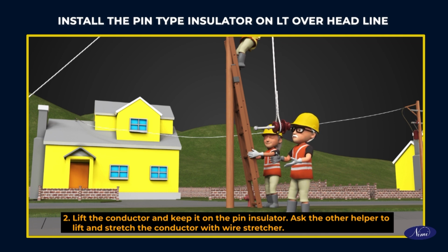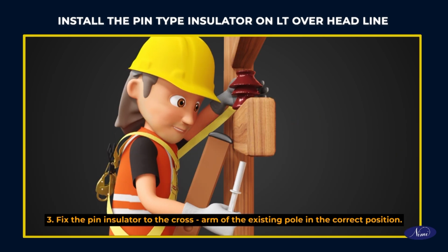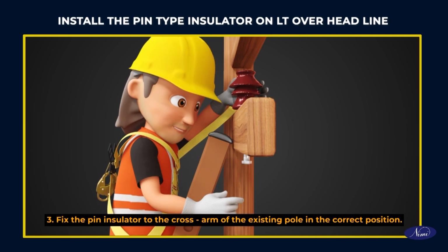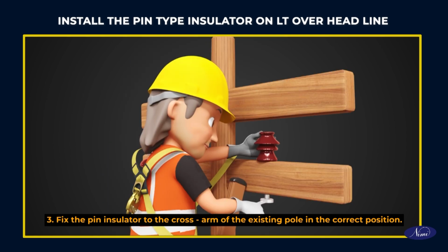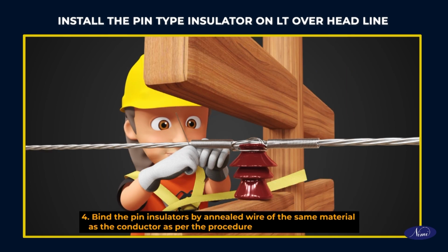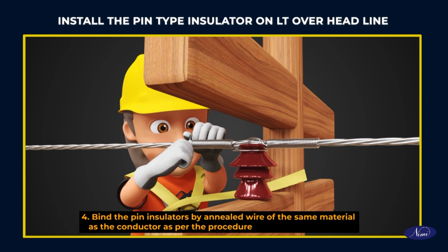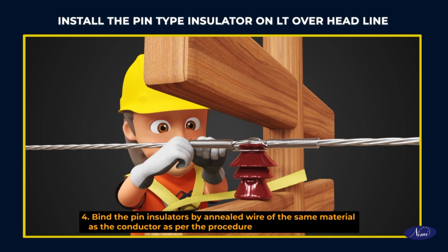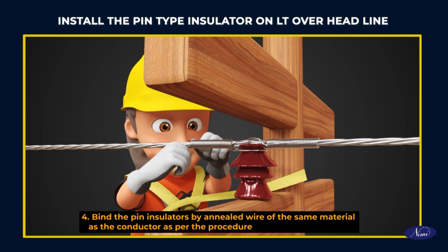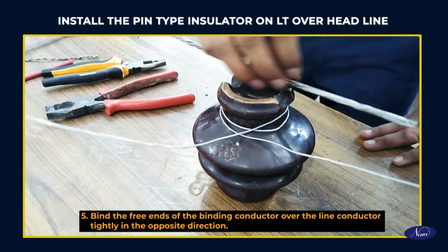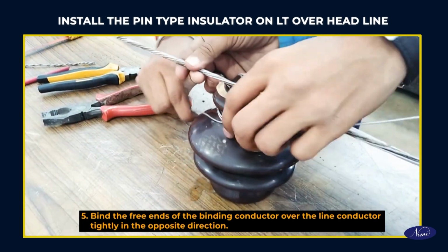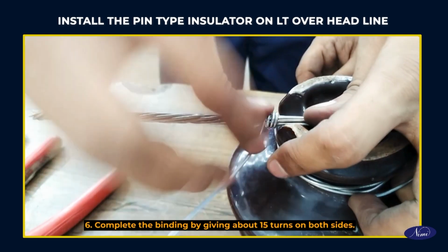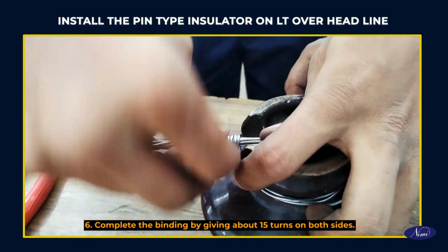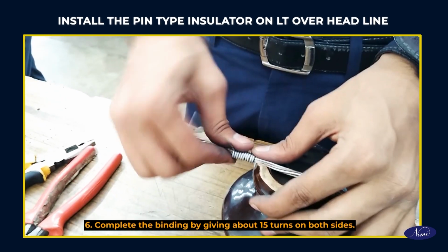Ask the other helper to lift and stretch the conductor with wire stretcher. Fix the pin insulator to the cross arm of the existing pole in the correct position. Bind the pin insulators by annealed wire of the same material as the conductor as per the procedure. Bind the free ends of the binding conductor over the line conductor tightly in the opposite direction. Complete the binding by giving about 15 turns on both sides.